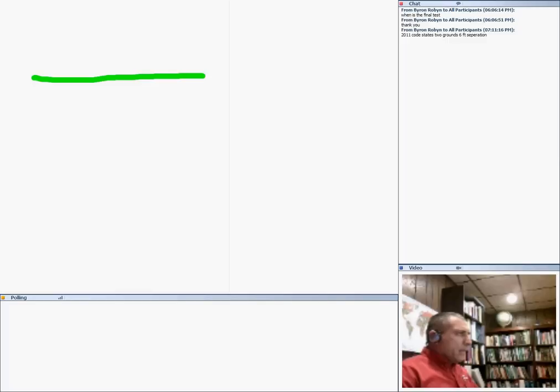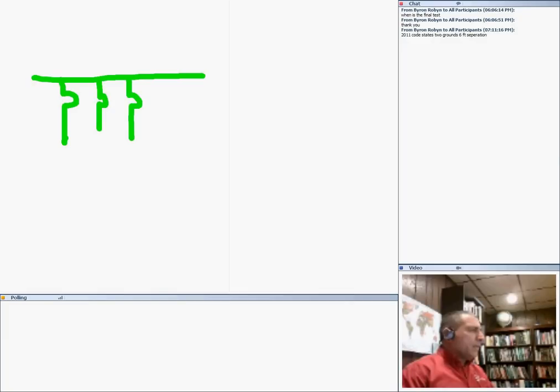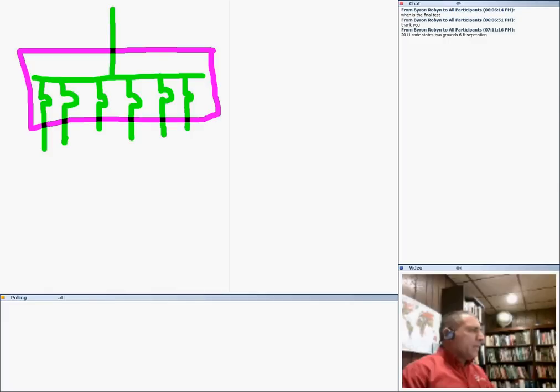Suppose I have an apartment building, and I have apartment 1, apartment 2, apartment 3, apartment 4, apartment 5, and apartment 6. Up to this, I can have my conductors tied without a main. So here's my switchgear, basically, or switch panel. Can you guys see there is no main for this panel? Because each one of these would be one of the 6 disconnect rules. Remember the 6 disconnect rule: you can have 6 disconnect services grouped in one location without a main. The minute that you add a 7th one, say I add the 7th one here, then you have to go and put an overcurrent protection device right here.